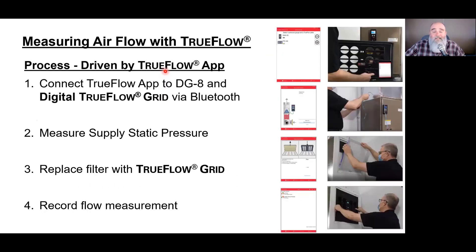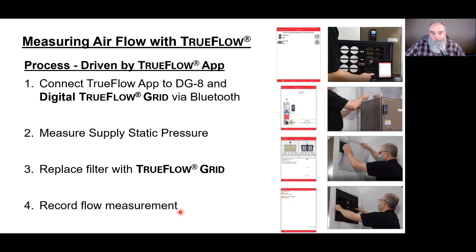The process is driven by an app — it's quite simple. As you can see in the photographs, Steve's making a hole in the supply duct and we're going to measure that supply static pressure. We are going to remove the filter in the system and simply replace it with the TrueFlow grid, and with that it's going to record an airflow measurement.